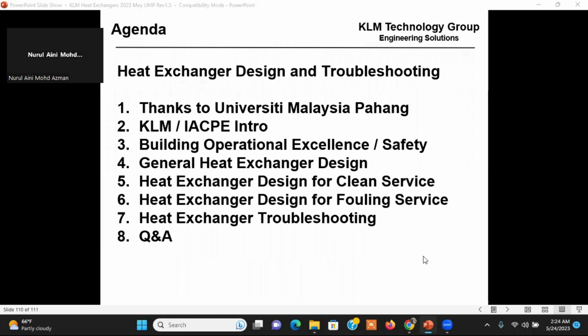My name is Lee. May I ask, if fouling occurs as shown in the slide, is it possible to restore the heat exchange by cleaning or maintenance, or should we design a new heat exchanger? The pictures that I showed, you can clean them, put them back in service, but they're going to foul again. If you put the notches in, which you could do easily, you'll get more heat exchange in the life of the heat exchanger. You don't have to buy a new heat exchanger. You can just clean them. But obviously the heat exchanger that fouls has very low efficiency.